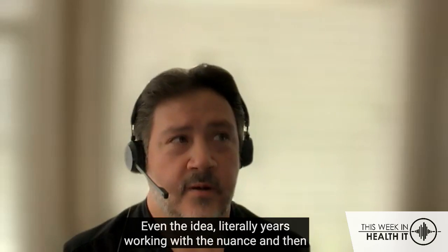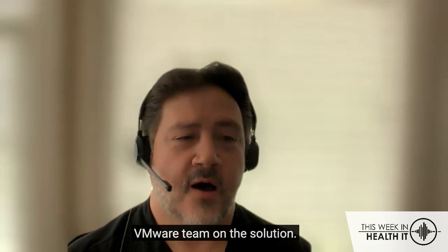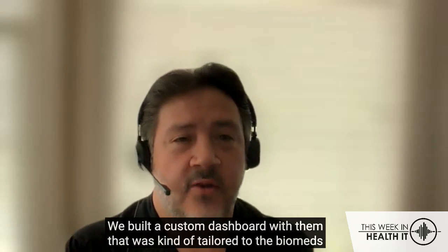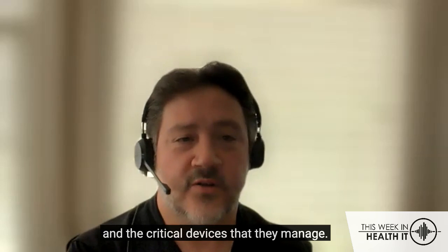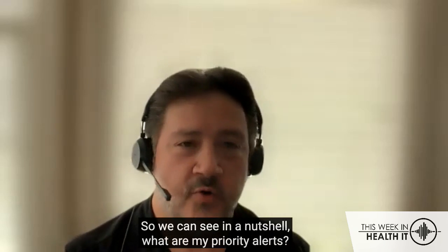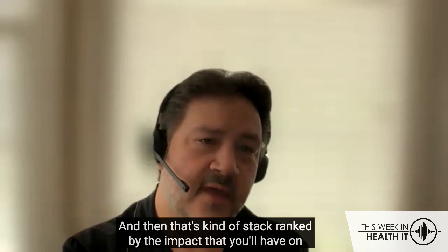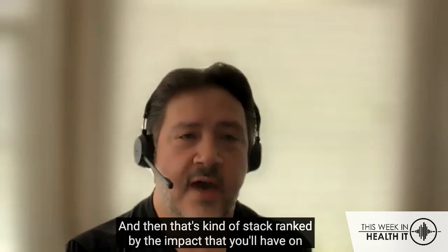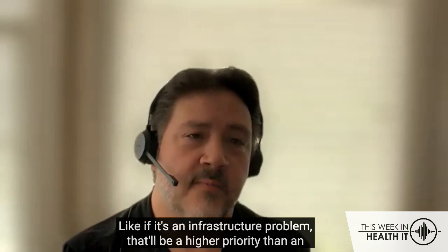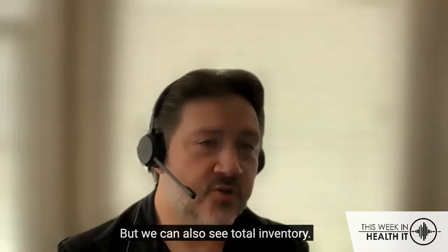We spent literally years working with the Nuance and then VMware team on the solution. We built a custom dashboard with them that was tailored to the biomeds and the critical devices that they manage. So we can see in a nutshell, what are my priority alerts? What are my problematic devices? And that's stack ranked by the impact that you'll have on the hospital or on the people. If it's an infrastructure problem, that'll be a higher priority than an individual device that's having an issue. But we can also see total inventory.